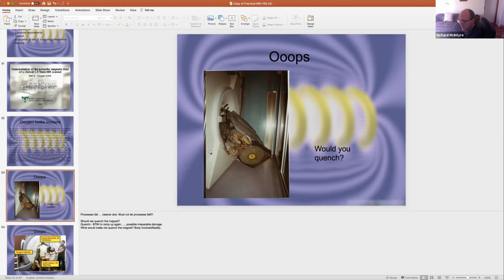So this happened at Monash Medical Centre. A cleaner took a floor buffer into the machine, and the floor buffer, of course, got stuck to the back of the MRI machine. Of course we wouldn't quench the machine, we wouldn't stop that magnetic field, because it's not an emergency. Whereas if the cleaner was stuck between that floor buffer and the machine, we would have to stop the magnetic field to get him out. That's a life-threatening situation. If we stop that magnetic field, it would cost about $260,000 to start it again. That's a lot of money.